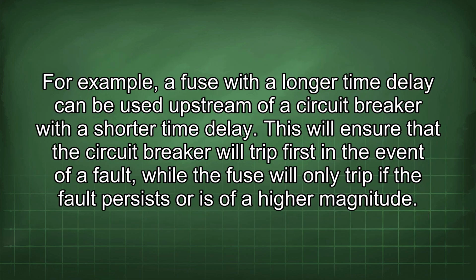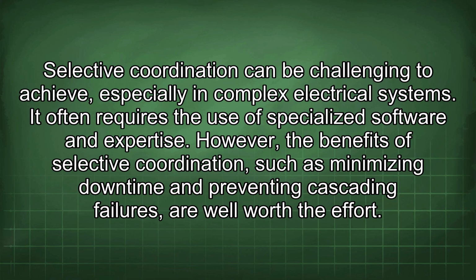For example, a fuse with a longer time delay can be used upstream of a circuit breaker with a shorter time delay. This will ensure that the circuit breaker will trip first in the event of a fault, while the fuse will only trip if the fault persists or is of a higher magnitude. Selective coordination can be challenging to achieve, especially in complex electrical systems. It often requires the use of specialized software and expertise. However, the benefits of selective coordination, such as minimizing downtime and preventing cascading failures, are well worth the effort.